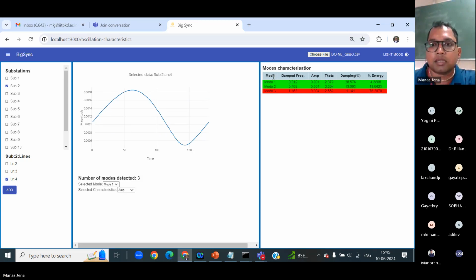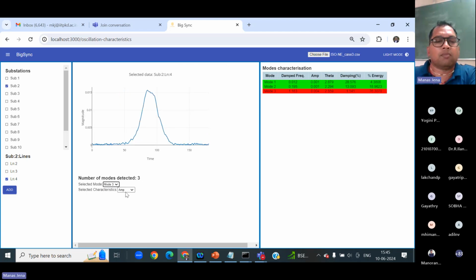You can see 3 modes it is showing, but the first 2 are having good damping, 28% and 13%. Any power system operator will know that these are good damping actually. This particular mode, 1.16 Hertz with 1.14% damping, is a dangerous mode because the damping is less than 5%. Okay, and energy contribution is also more. So this mode 3, I need to dig into this mode 3, right? So the user can select mode 3 amplitude. You can see the mode 3 amplitude, that means this mode 3 got excited because of some event in their system, and you can see their amplitude.